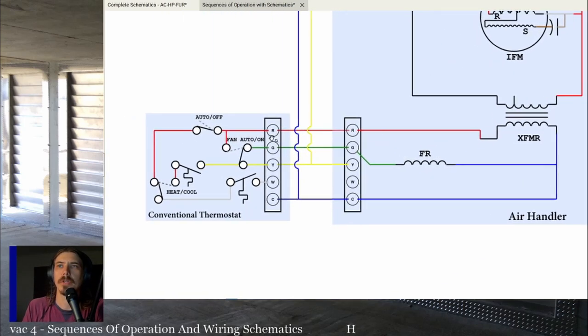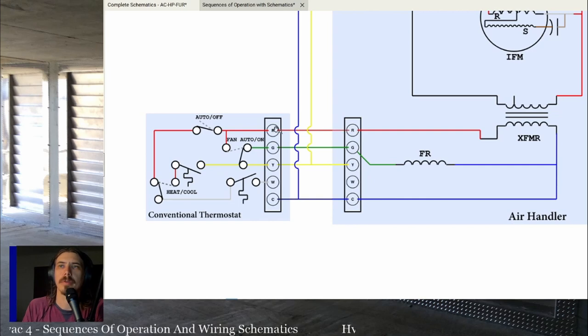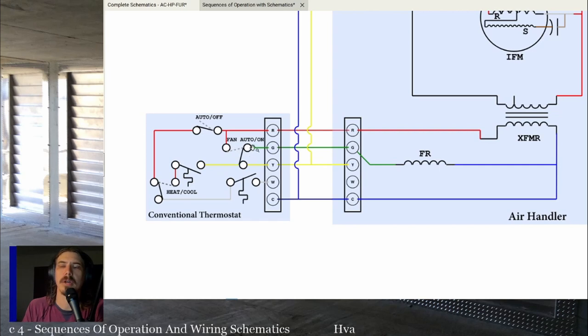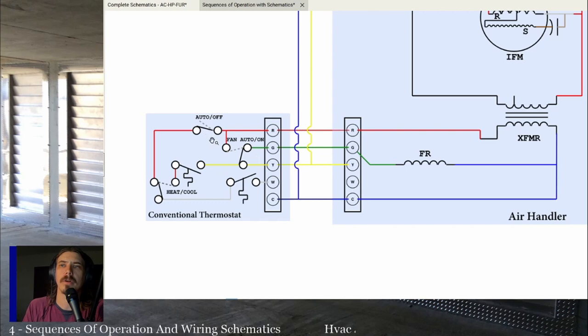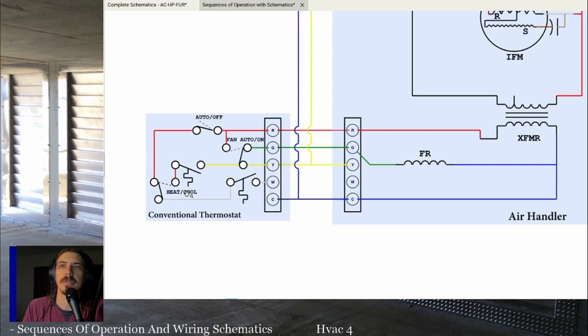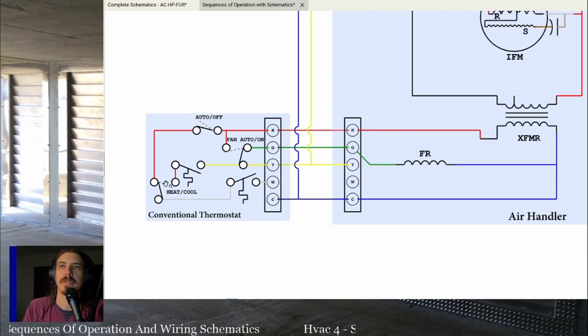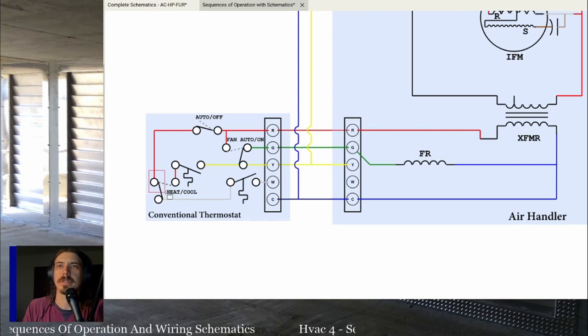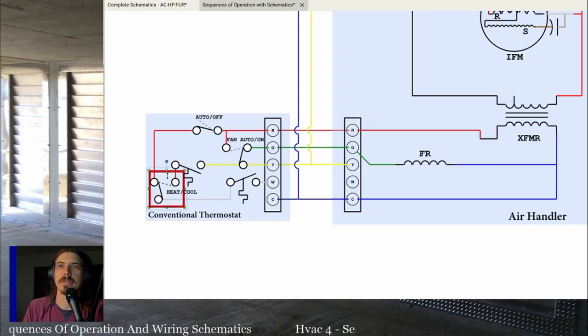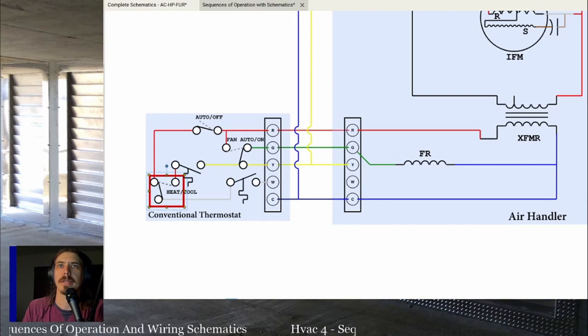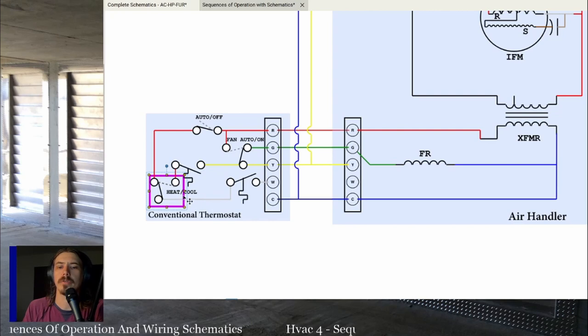Moving over to the thermostat: R goes to the thermostat and connects to one side of the fan auto/on switch — currently shown in the auto position, with 'on' being the other position. Power immediately goes to that switch so you can have the fan on or off. If the system is in auto, it'll automatically work in heat or cool wherever it's set. There's also a heat/cool switch — that's what selects whether you are in heat or in cooling.